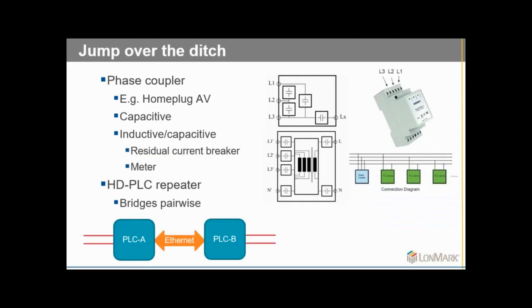The good news is, since we are using the same frequency range as HomePlug, we can use off-the-shelf products that already solve the problem for HomePlug, phase couplers. You can have simple capacitive phase couplers, but they introduce a small leak current between the phases. So you are not allowed to use that in case of jumping over a current breaker or jumping over a meter, because if you use that to jump over a meter, it will change the metering results. For that case, we have in the market some combined phase couplers, which are both inductive and capacitive. So you need to take care when doing the electrical installation.